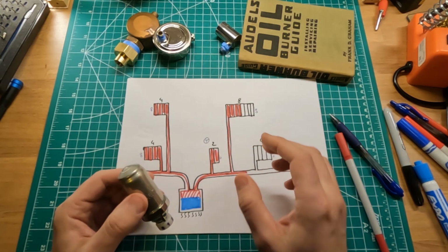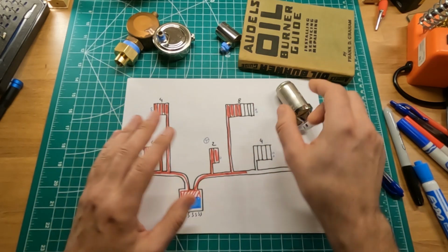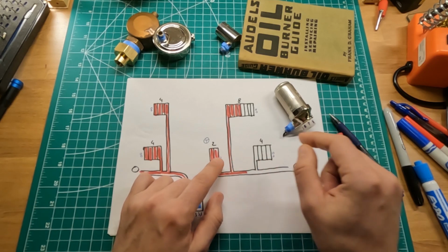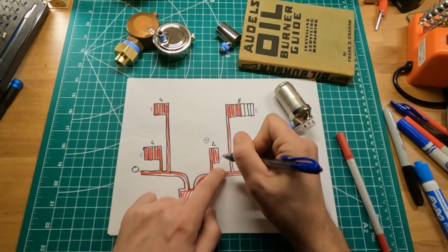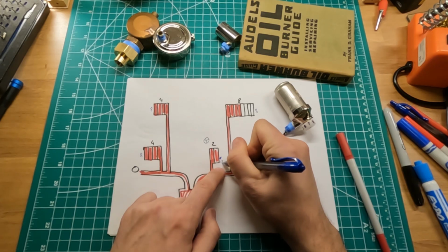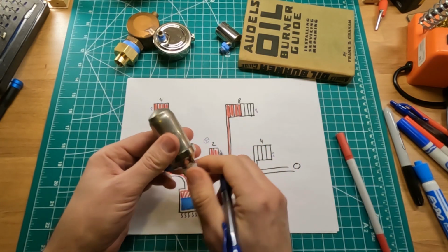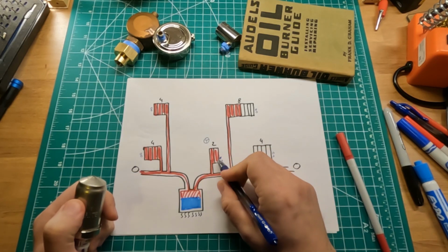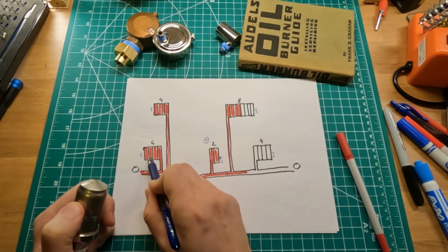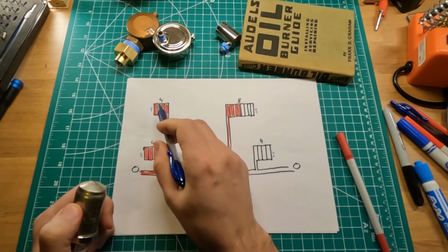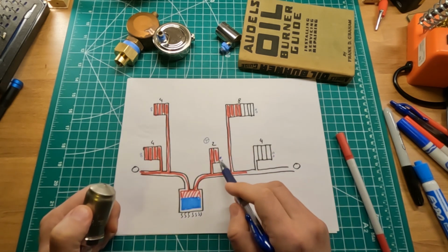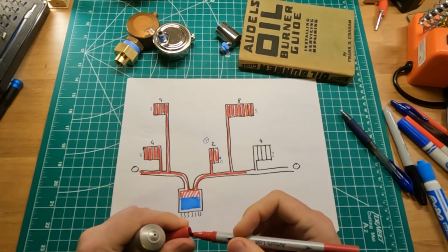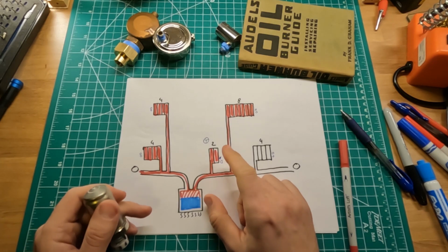There are two solutions. One solution is to decrease the venting rate of this radiator. So instead of having one circle, you give it a half circle, if you can. That means you would throttle it down so that an even smaller amount of air comes out from this radiator. If you give this radiator a half circle, then those radiators will fill up totally, and this one with a half circle will heat up as well. So that would be one solution.